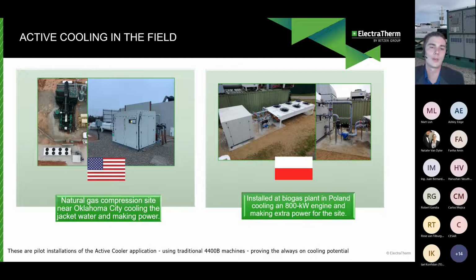So for example, if we're coupling to, say, a Cat 3616 engine, and we're making 50 kilowatts from jacket water, great, we're making a considerable amount of power. Well, if it was on electric coolers already, then we're also eliminating, say, 10 to 20 kilowatts of electric load that's already at the site. So you're actually netting 60 to 70 kilowatts at that particular site just from the jacket water.